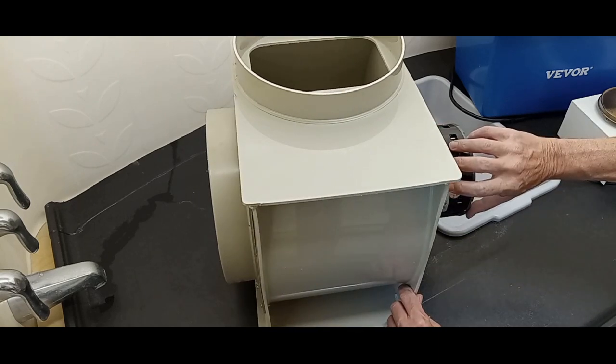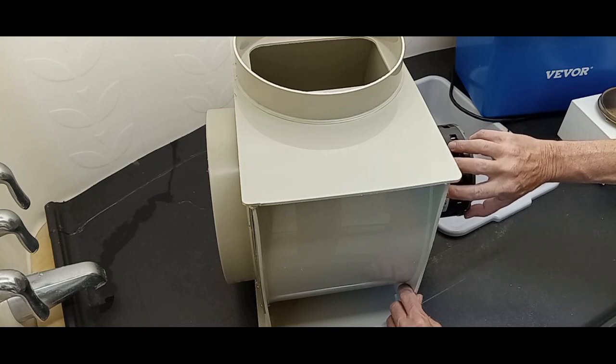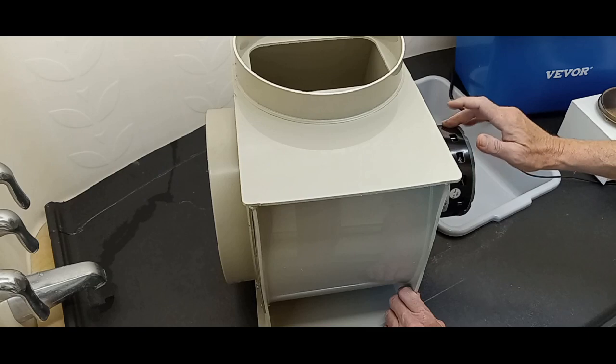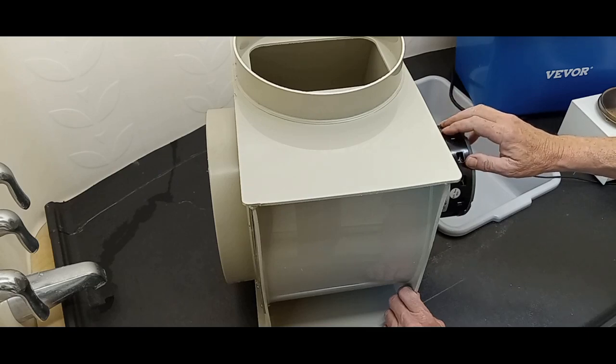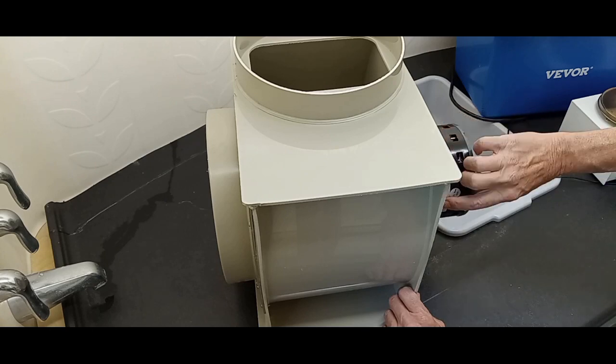According to this, the black is low, the blue is medium, and the red is high, coming back to the yellow, which has a thermal switch in the motor as they should, hopefully self-resetting thermal switch.